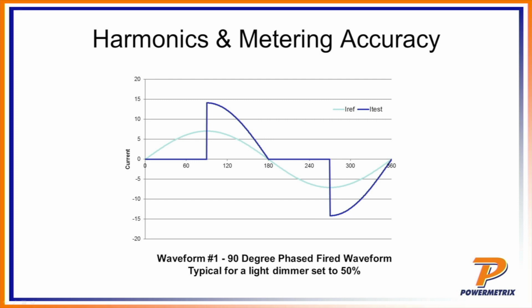This has a lot of harmonic energy. Once again, if you have a very sharp edge, that sharp edge produces a lot of harmonics. So this is probably one of the worst harmonic loads of the 6 waveforms being defined by ANSI. This particular waveform is defined up to the 20th harmonic as the minimum that the meter manufacturers have to test for. It could easily be generated all the way up to the 100th harmonic.